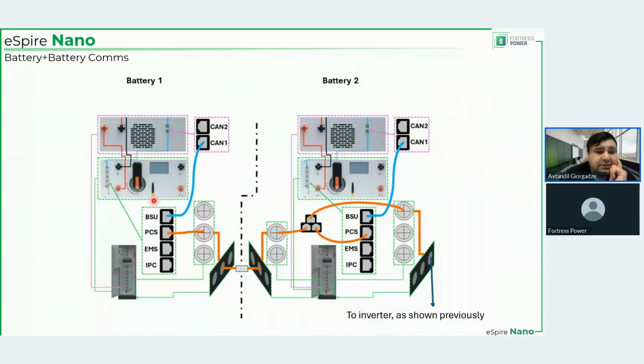Battery two connects to battery one via splitter. So that communication splitter connects the PCS port of battery number two to the PCS port of battery number one. And then you wire the communication from the splitter to the inverter, just like I showed you before, for one battery between the PCS and the inverter. Again, conduits are provided by the installer. This communication cable, I mean, yes, there's a good chance that you will find the length enough for the included communication cable with the batteries to run between the two batteries.